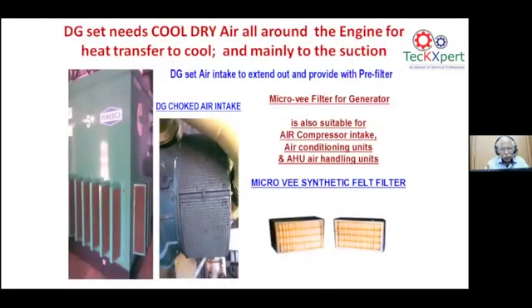Cool, dry air to the genset. Again, what has been told about the compressor applies to the genset also. You can see the genset with this air intake filter. It is a totally choked filter, and this generator is running for more than 12 hours a day. The output is totally staggered and fluctuating because of the choked air intake filter at the genset. It can be corrected by a micro V-type filter with two-stage filtration.